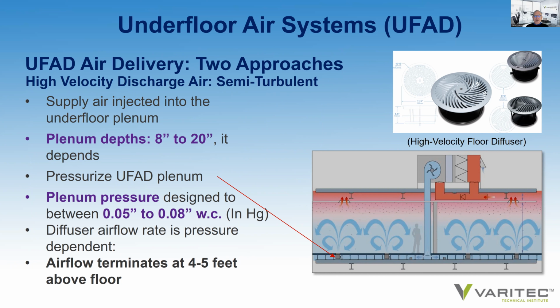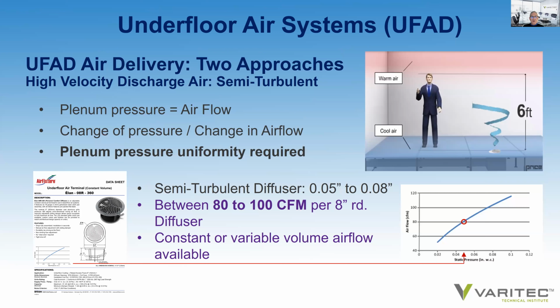Air in these semi-turbulent designs terminates at about 4 to 5 feet above the floor, thereby creating an occupied zone of mixed air and a uniform temperature throughout the occupied zone. So plenum pressure equals airflow, change of pressure equals change in airflow. Plenum pressure uniformity is required. A semi-turbulent diffuser designed at 0.05 to 0.08 inches supplies air at a volume of 80 to 100 CFM per 8-inch diffuser. Now be aware, manufacturers make 10-inch diffusers, and there are even some rectangular or square diffusers that provide even more airflow in areas where you don't need to have that dedicated diffuser for occupants to improve the indoor air quality at that occupant's breathing zone.